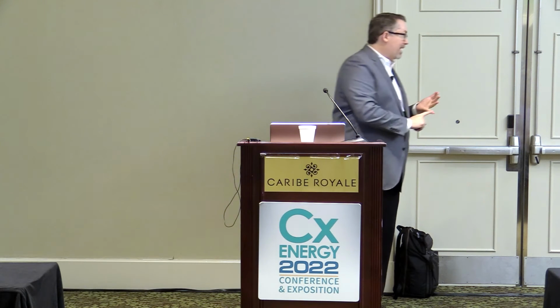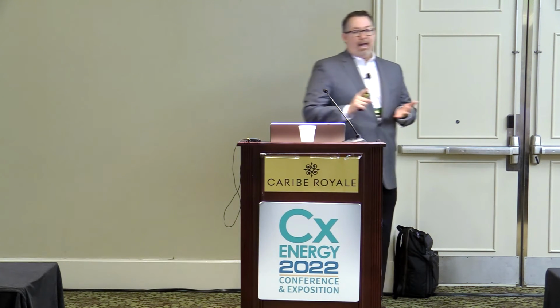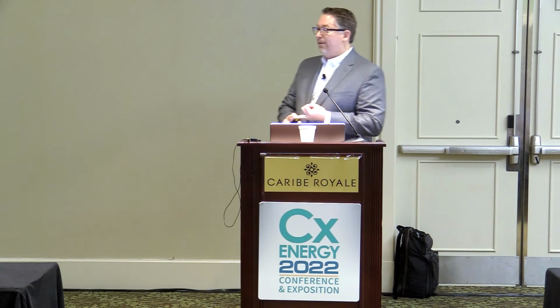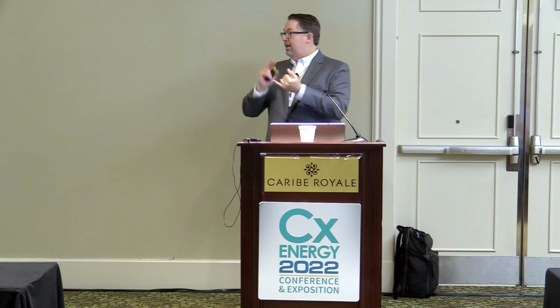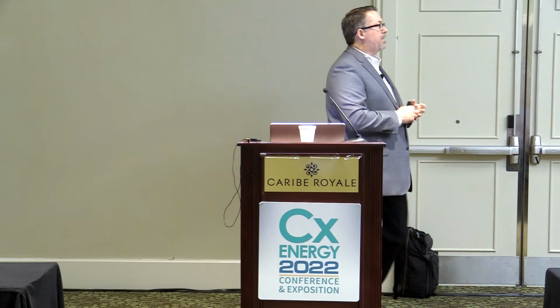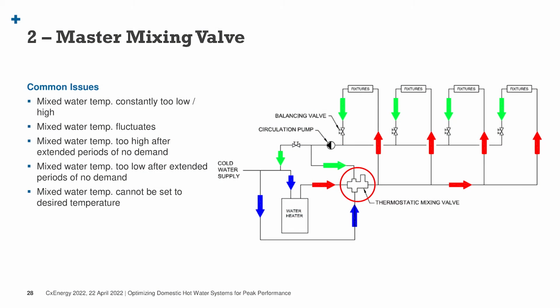Am I generating the hot water temperature that I want? And am I providing enough hot water at peak demand? And if I'm not, then it's potentially my water heater that's the issue. So you start there. If you've got the right hot water coming out, you've got enough to meet the peak demand, move on to your mixing valve. Mixing valves are notorious. I put thermostatic here because those tend to have more issues, be a little more sensitive to how they're installed than some of the digital mixing valves.